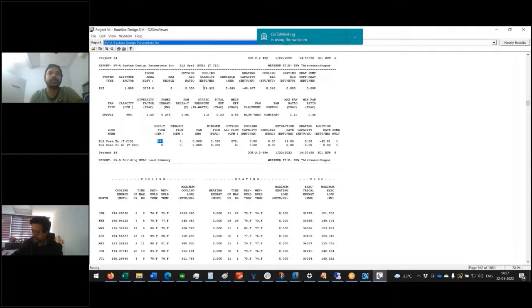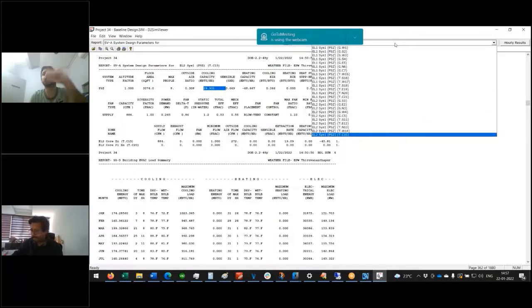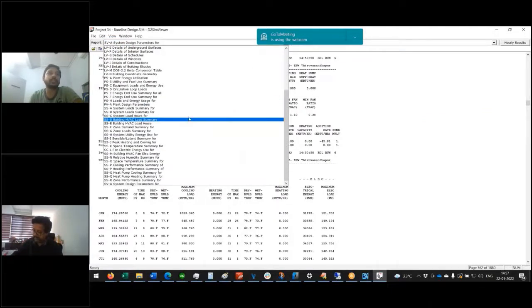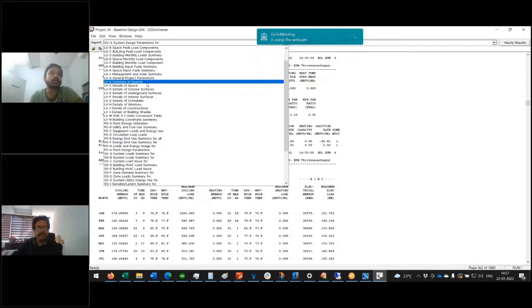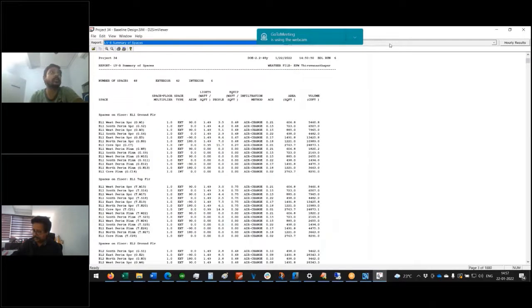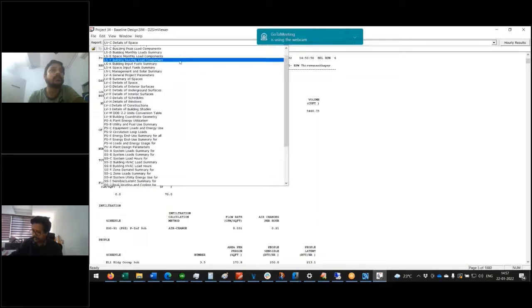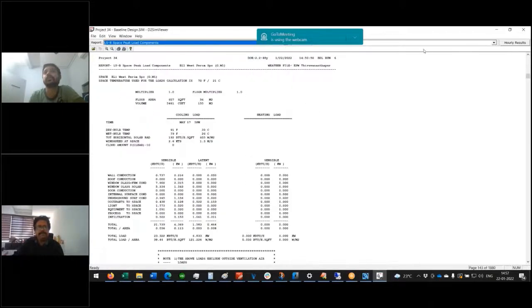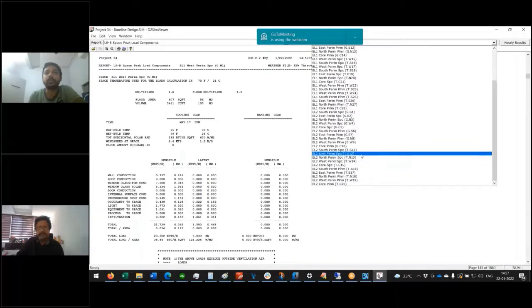Okay, so in fact, what we see over here is that 29.931 is the system auto-sized capacity. Let's look at the peak load for this specific space TC15. So that we can see from, I think, summary of spaces. Oops, not summary. Let's go to details of spaces. Yeah, here the details. There should be building loads, building monthly space, monthly load components, space peak load components. Yeah, let's go to this one, and let's go to TC15.